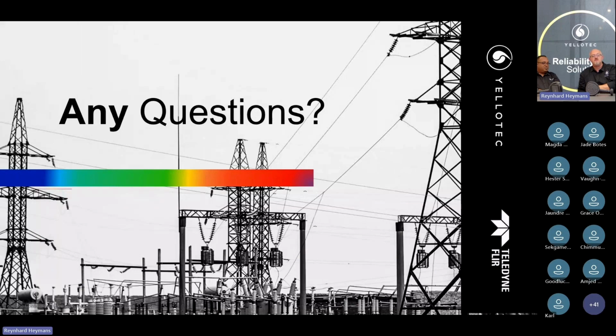Does the unit detect the distance, or does the operator need to input it? With the FLIR LD Plus unit, it automatically detects the distance. However, with the other units, you've got to manually put it in. That's still relative, since you can often judge distance without being extremely accurate, or judge exactly what distance you're away. You can also put the distance into the device itself or into the software when using it.